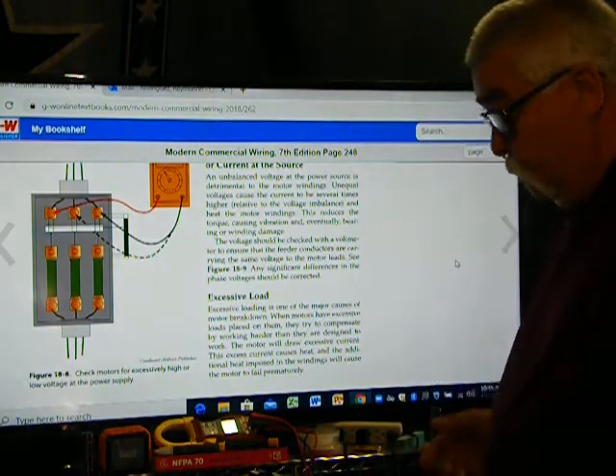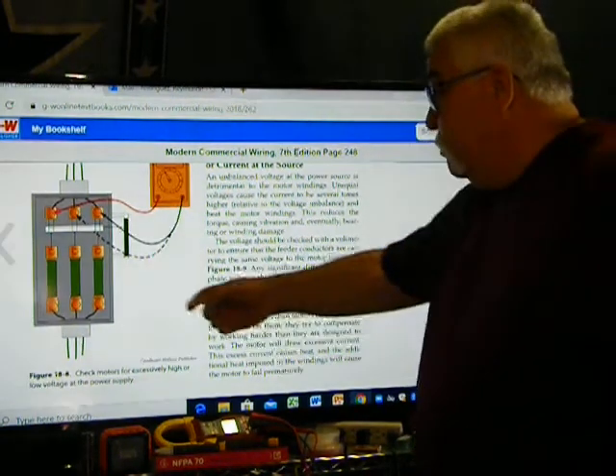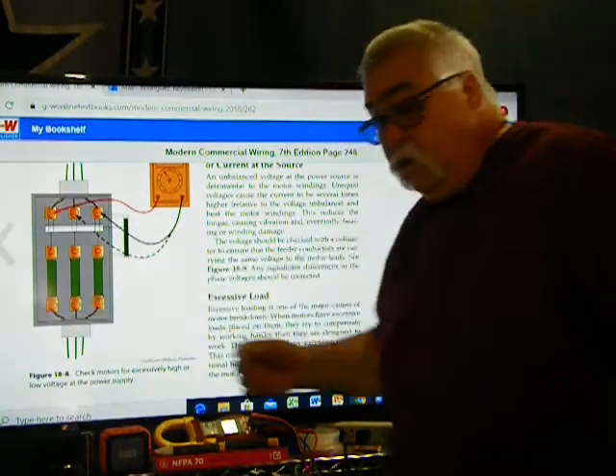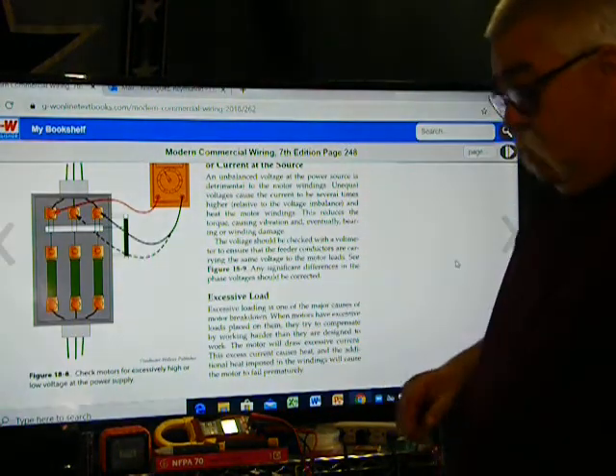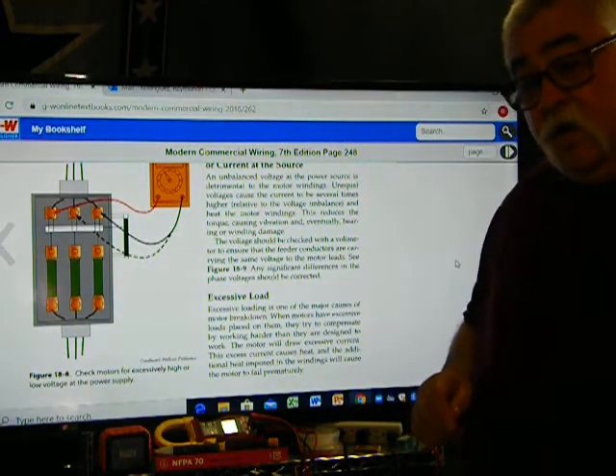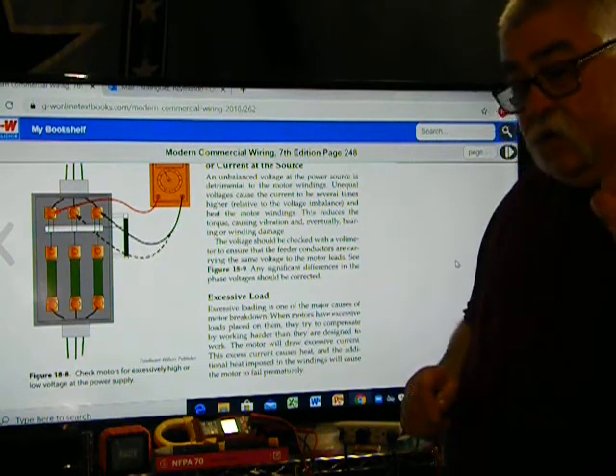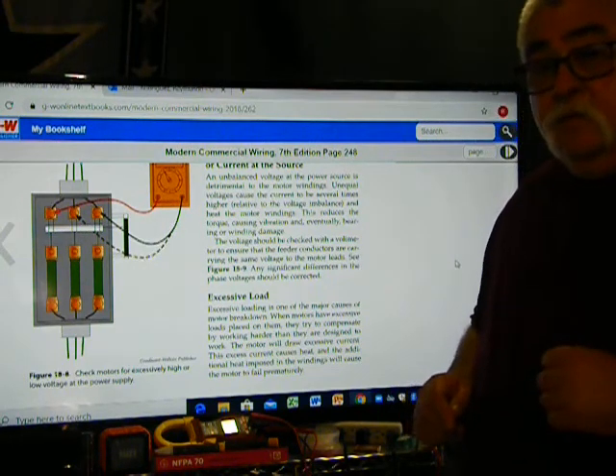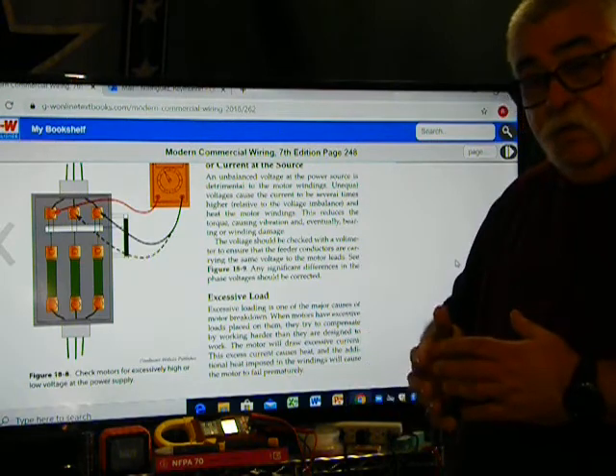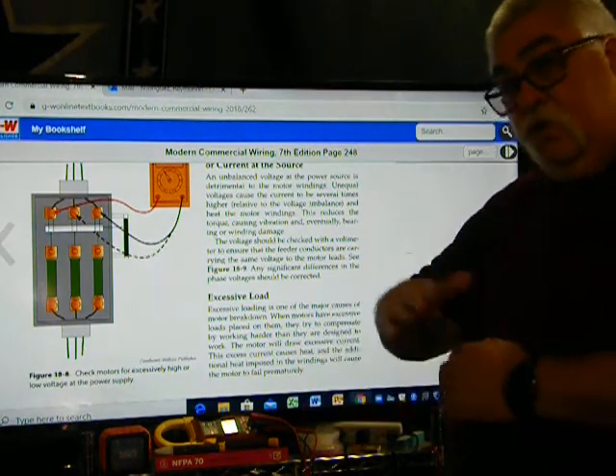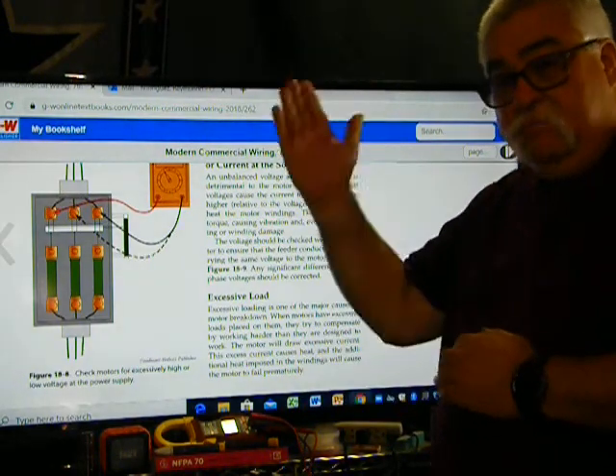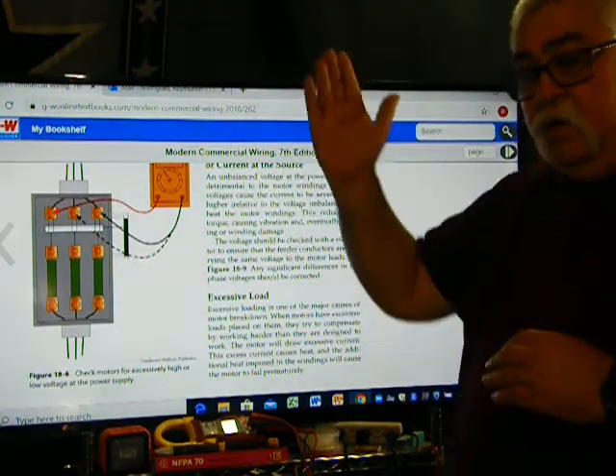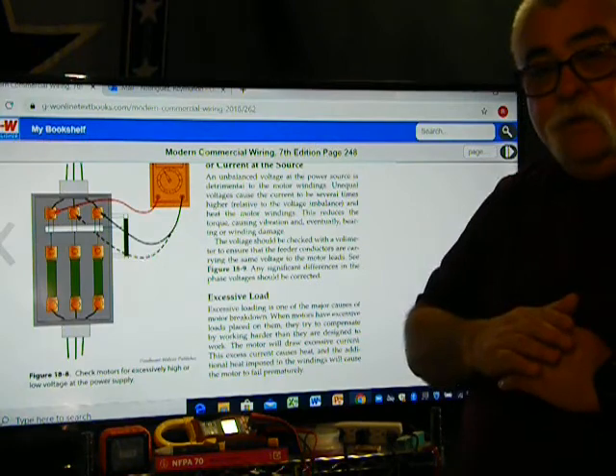So in that case, you get your amp probe, check the current, and make sure your current is balanced. Make sure that your current is not exceeding the rating of the motor, because the motor's been designed to handle so much current. Yes, there's a starting current, but that's only minimal. It runs for a couple of seconds and back down. Once a motor turns on and gets up to full peak, it comes back down.